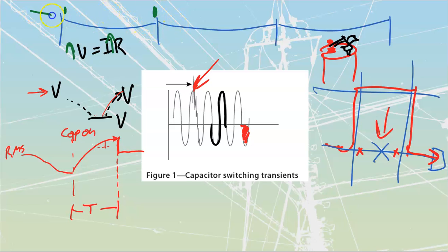Because I drop a lot of volts across this line section, I end up with less volts further along, and even less further on if I've got different consumers tapping off these lines. We're supposed to stay within plus or minus 5% for our voltage value, so you do the math based on the type of system you have—it shouldn't stray far past that.